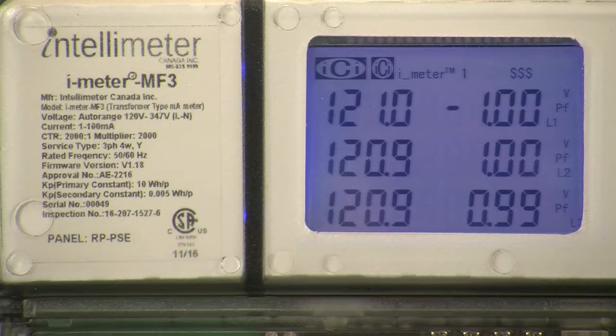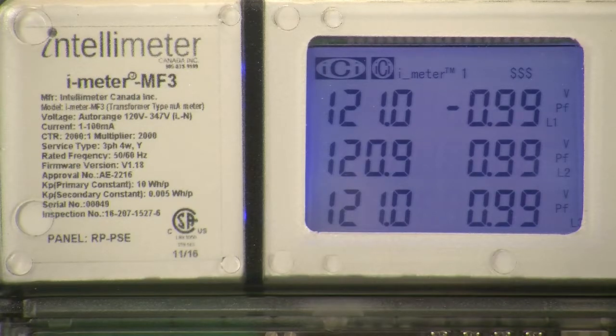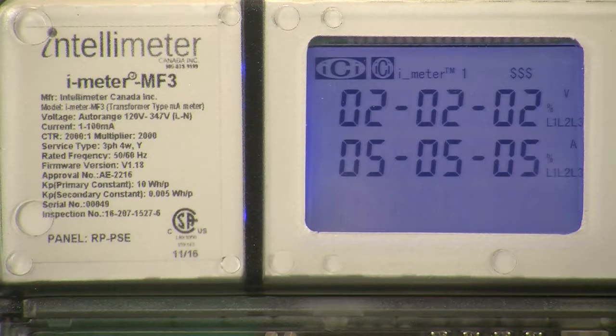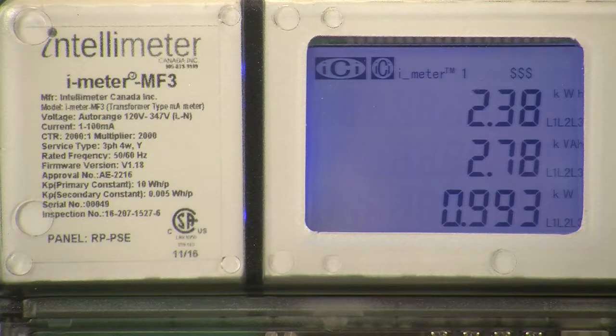Make sure that the black CT lead wire is in the negative terminal, and the white CT lead wire is in the positive terminal. If everything just mentioned checks out, then there is most likely a problem with the reference voltage. You're going to repeat the phase test that was covered previously in this video, and ensure that line 1 on your reference voltage is on phase A, and that CT1 is installed on phase A as well.